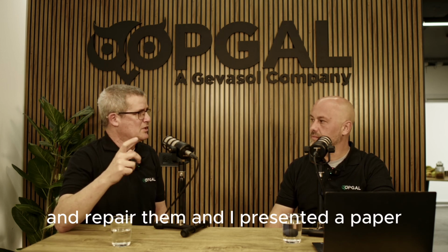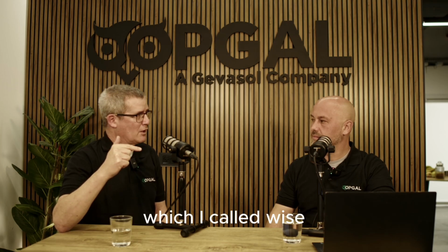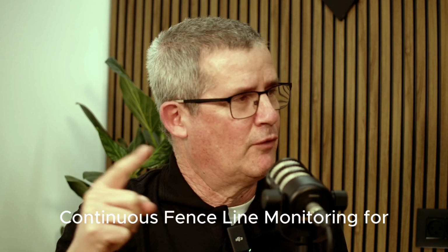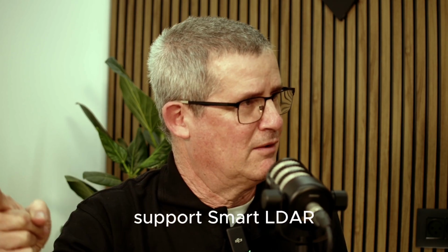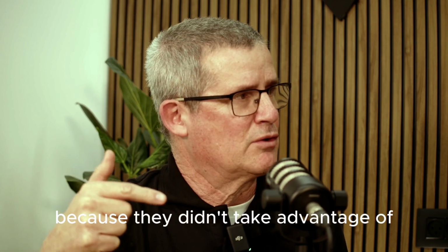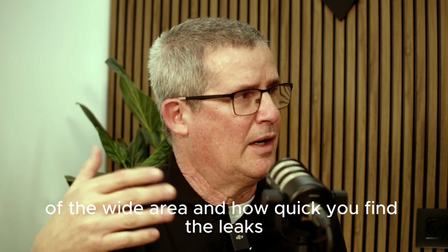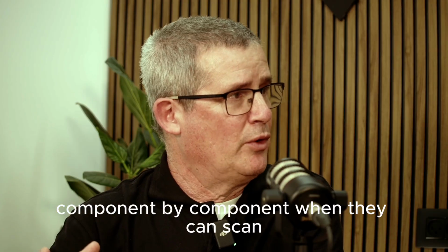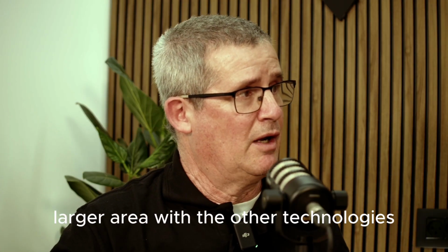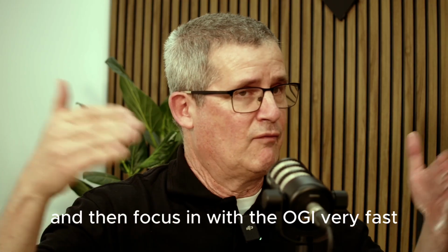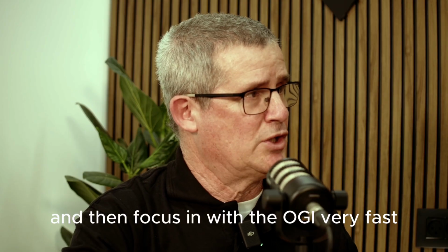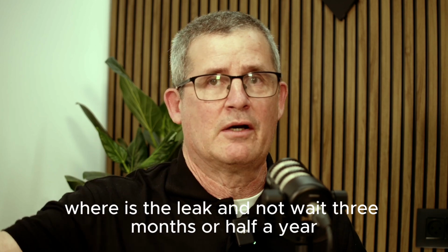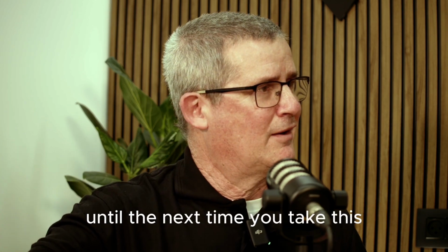And I presented a paper which I called Wise Continuous Fence Line Monitoring for Support Smart LDAR, because they didn't take advantage of the wide area and how quickly you find the leaks. They still went with the routine component by component, when they can scan a larger area with the other technologies and then focus in with the OGI very fast on where the leak is, and not wait 3 months or half a year until the next time you take this.